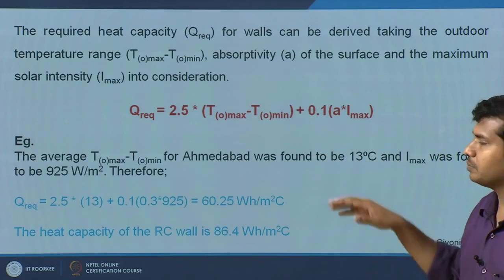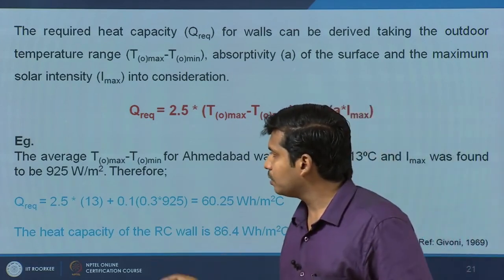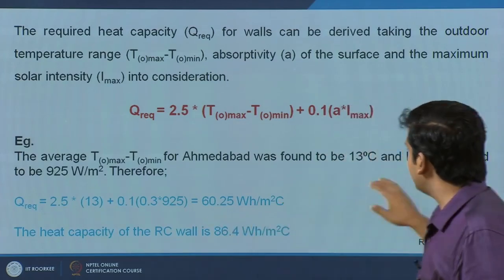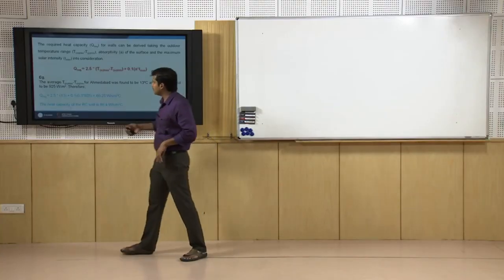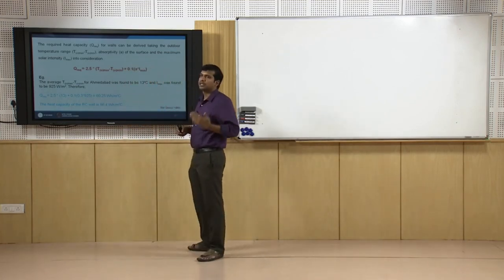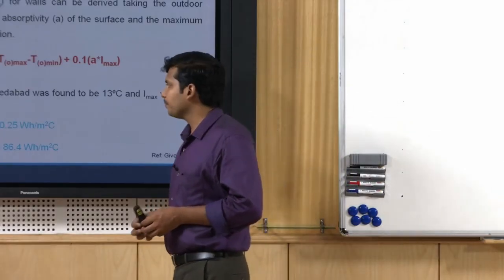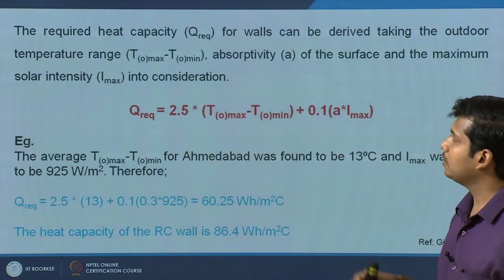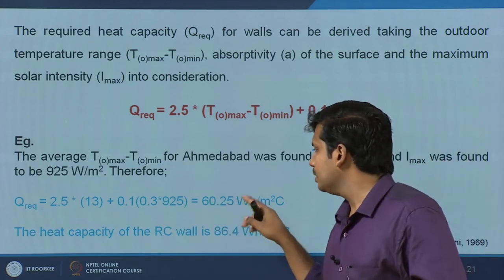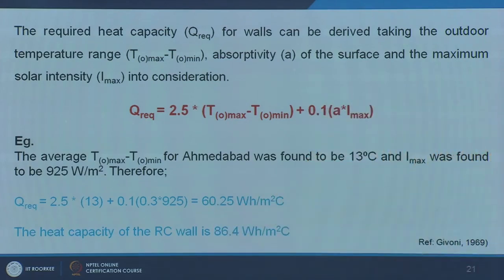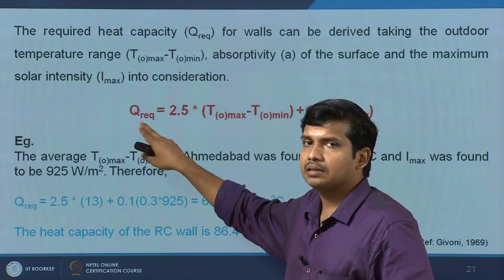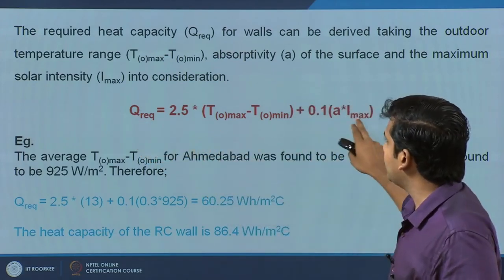Substituting values for Ahmedabad — a hot and dry climate per the national building code — we took a day where ambient temperature delta T was 13 degrees and solar radiation I_max was 925 watts per meter square. With a wall surface absorption of 0.3 (a white-painted surface reflecting most solar), the required heat capacity Q is around 60 watt-hour per meter square per degree centigrade. As solar radiation intensity goes up, required heat capacity increases.